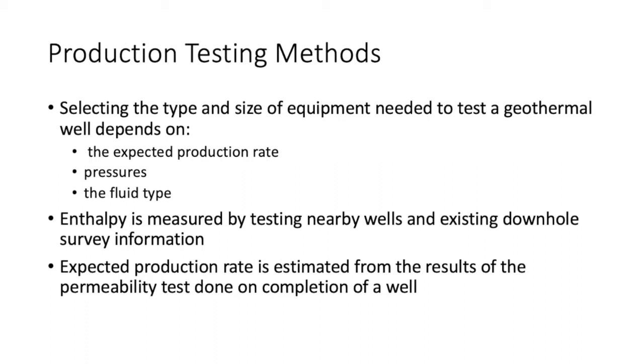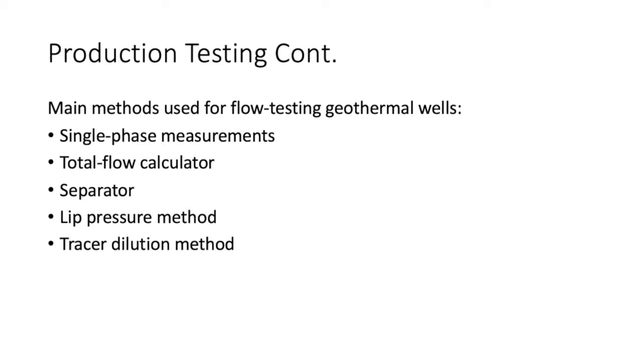Selecting the type and size of equipment needed to test a geothermal well depends on the expected production rate, the pressures of the well, and the fluid type. The expected fluid enthalpy will usually be known from testing nearby wells and downhole survey information. Expected production rate is estimated from permeability test results at well completion. Where environmental conditions permit, a brief vertical discharge directly into the atmosphere can be used with the lip pressure method to get a first estimate of long-term production potential. The main methods used to flow test geothermal wells are single-phase measurements, total flow calorimeter, separator, the lip pressure method, and the tracer dilution method.